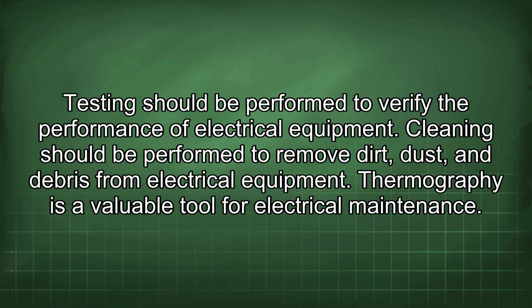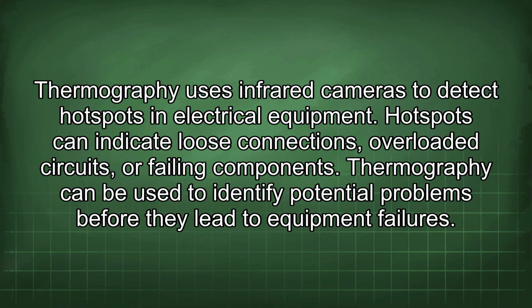Thermography is a valuable tool for electrical maintenance. Thermography uses infrared cameras to detect hotspots in electrical equipment. Hotspots can indicate loose connections, overloaded circuits, or failing components. Thermography can be used to identify potential problems before they lead to equipment failures.